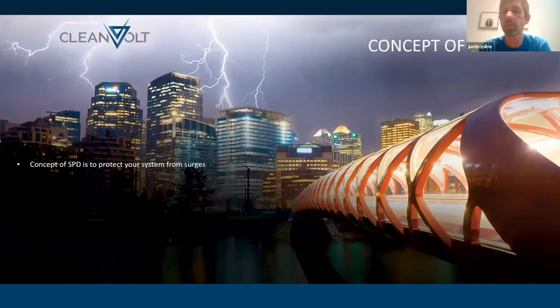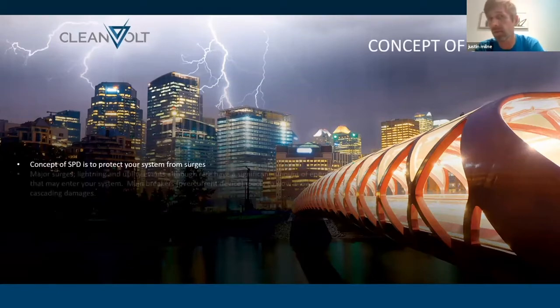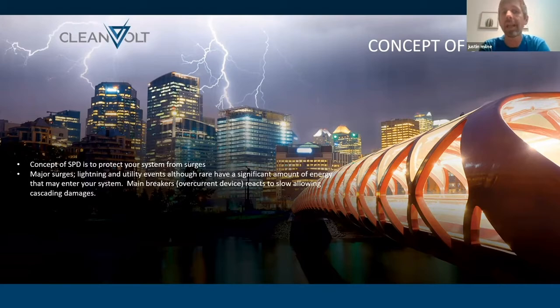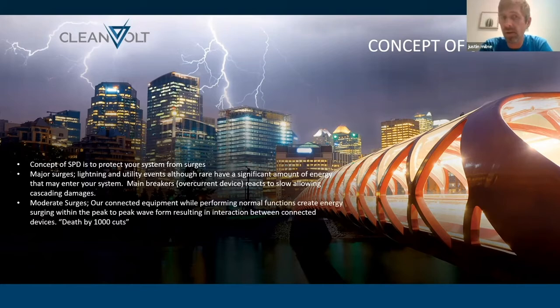The concept of a surge protection device, of course, is to protect your system from surges. When it comes to lightning and utility events that have a significant amount of energy that may want to enter your system, your main breaker or overcurrent device reacts too slowly, usually allowing cascading damages. When it comes to moderate surges within our system, our connected equipment, while performing their normal function, create energy surges within the peak-to-peak waveform, resulting in interaction between the connected devices. We like to refer to this as death by 1,000 cuts.